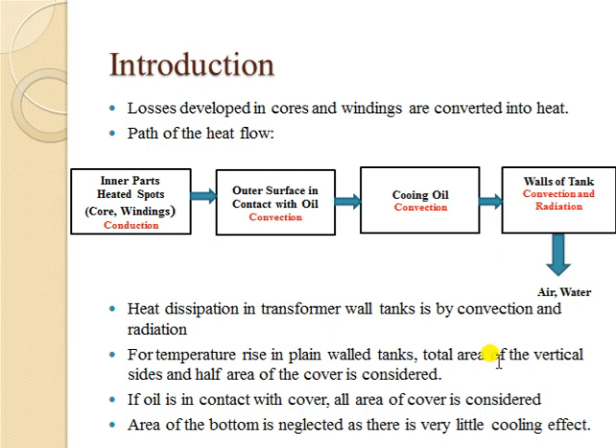If you picture the transformer as a cubicle, you consider the vertical sides and half the cover when calculating the number of cooling tubes. If oil is in contact with the top cover, then the full cover area is considered. The bottom of the transformer does not contribute much to cooling and is therefore neglected. These are the important concepts when understanding cooling tubes and overall heat exchange.